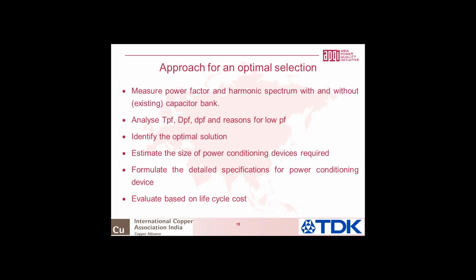Then estimate the size of the solution required. It is not like a transformer where the higher the capacity, the better the reliability, because you could actually end up making a mess of it. You'll have to choose whether you want 100 kVAR, 50 amps, 100 ampere. Then get the detailed specifications of the power conditioning device and evaluate it based on the life cycle cost. So these are some of the solutions for harmonics.